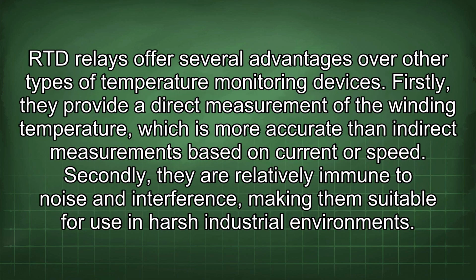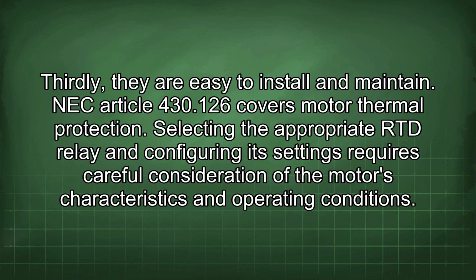RTD relays offer several advantages over other types of temperature monitoring devices. Firstly, they provide a direct measurement of the winding temperature, which is more accurate than indirect measurements based on current or speed. Secondly, they are relatively immune to noise and interference, making them suitable for use in harsh industrial environments. Thirdly, they are easy to install and maintain.